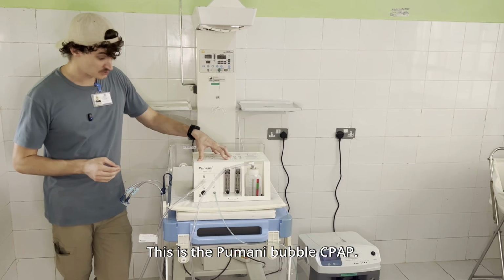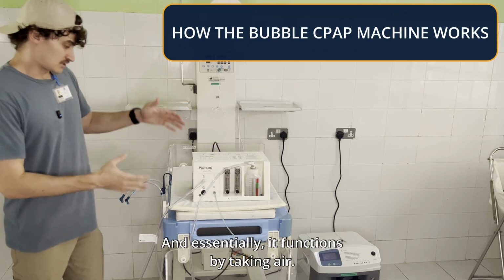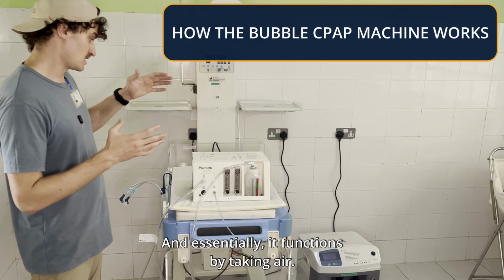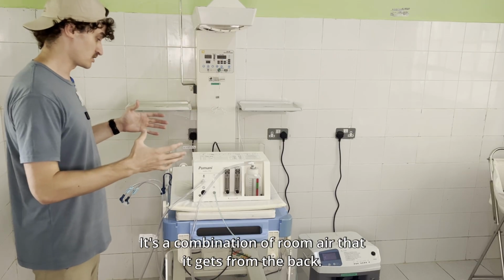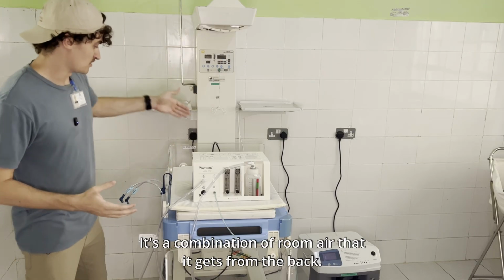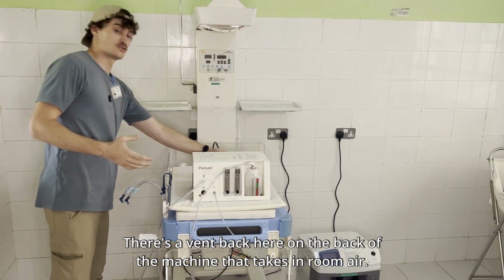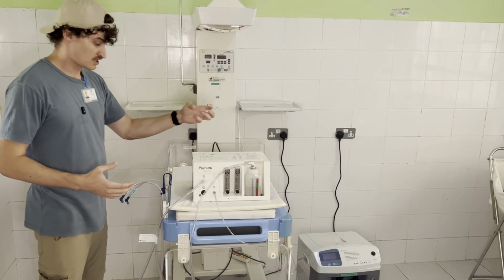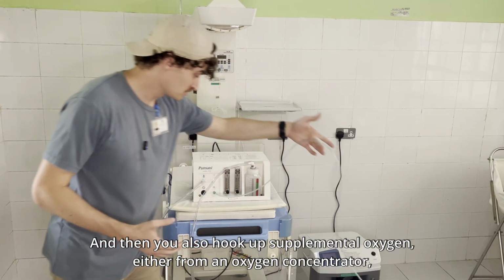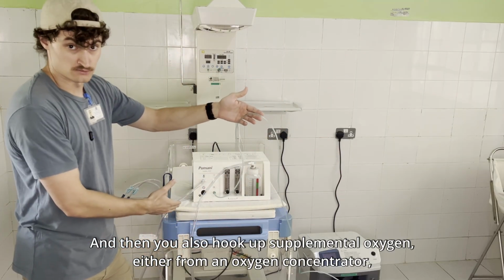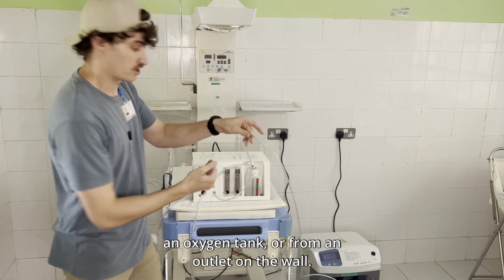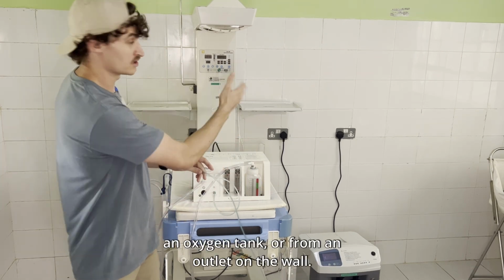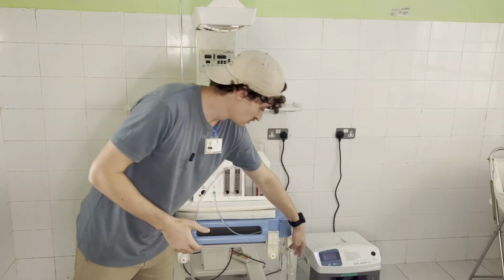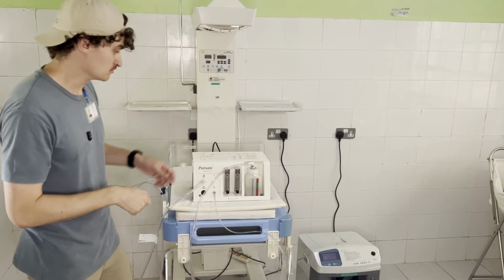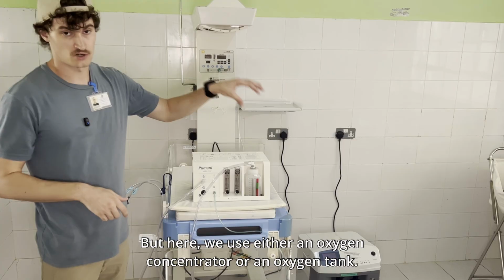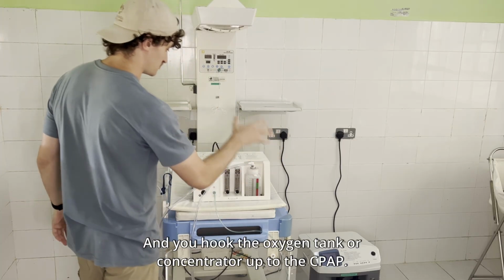This is the Pumani bubble CPAP, and essentially it functions by taking air. It's a combination of room air that it gets from the back. There's a vent back here on the back of the machine that takes in room air, and then you also hook up supplemental oxygen, either from an oxygen concentrator, an oxygen tank, or from an outlet on the wall that has oxygen. Some hospitals have oxygen outlets on the wall, but here we use either an oxygen concentrator or an oxygen tank, and you hook the oxygen tank or concentrator up to the CPAP.